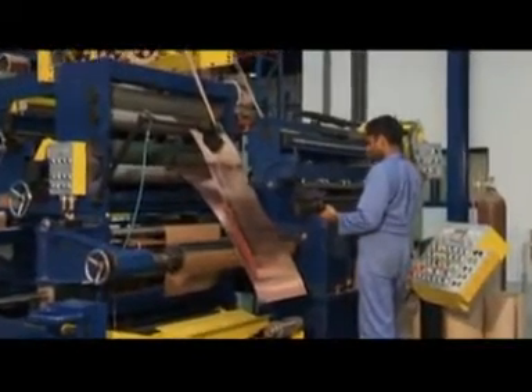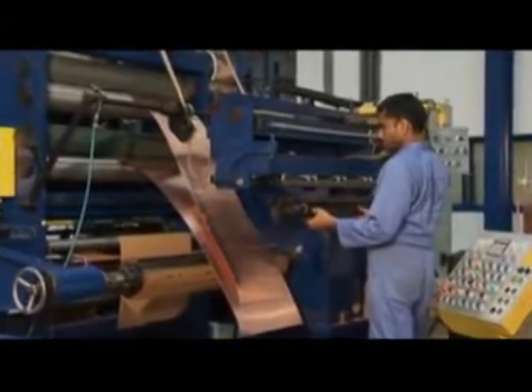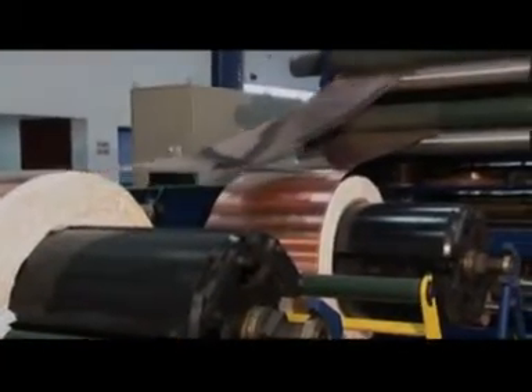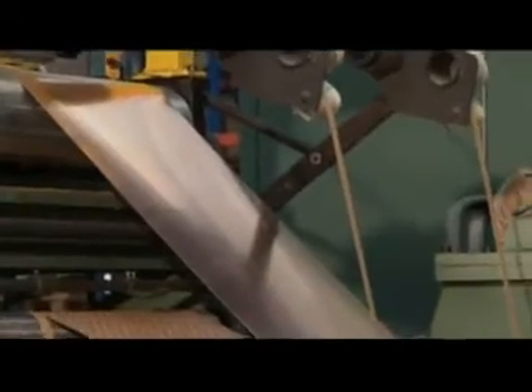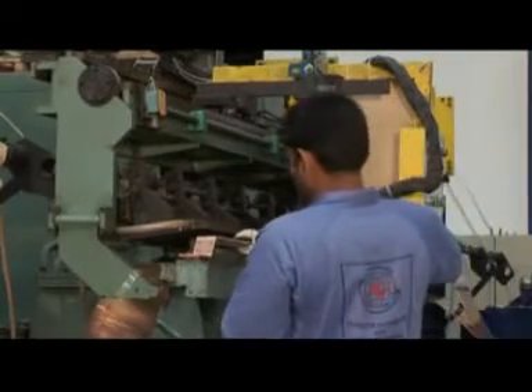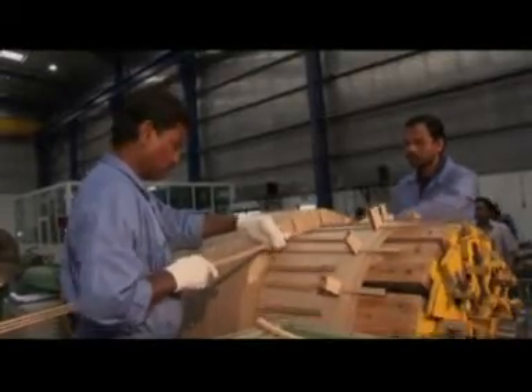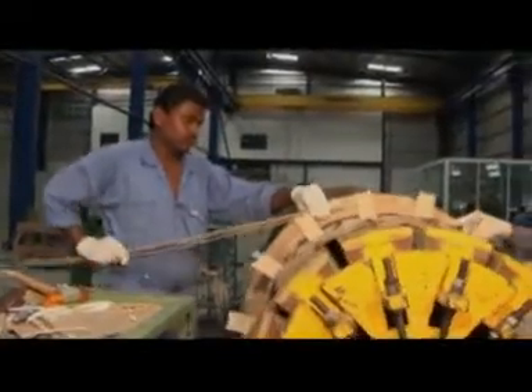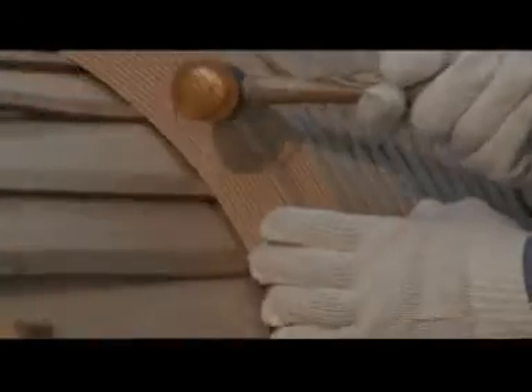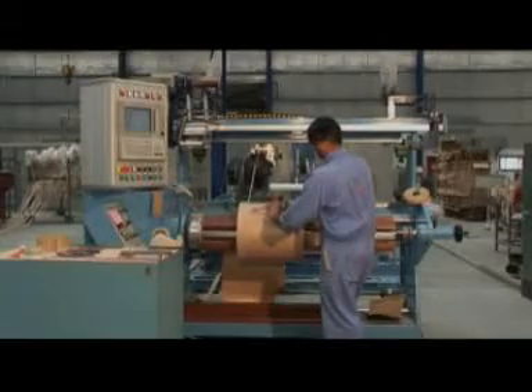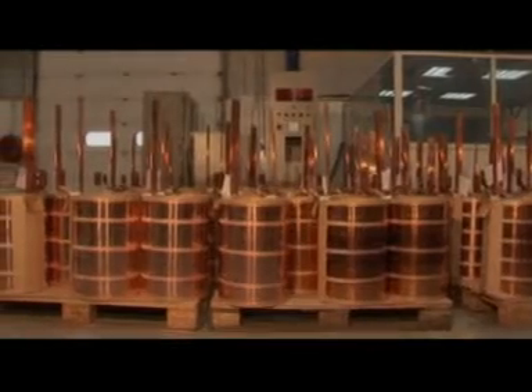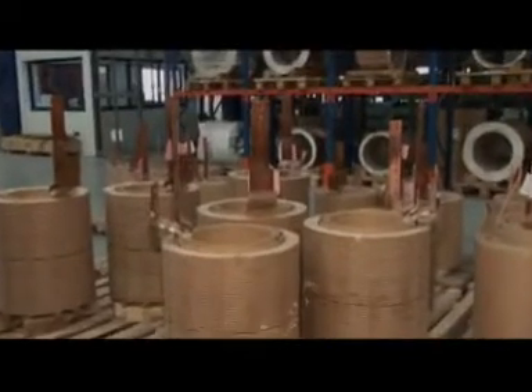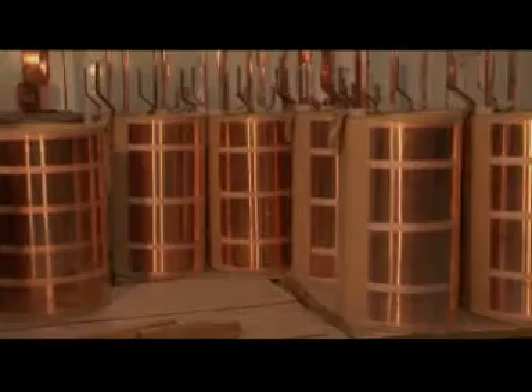Transformer windings are made of very high quality electrolyte grade copper strips. For medium range distribution class transformers, the LV windings are made with electrolyte grade copper foils. HV windings are made with rectangular or round copper conductors. Specially designed winding machines are used for making windings of power transformers. Multiple paper-covered copper conductors are used in making the coils for large power transformers. All windings are designed circular and concentric, which gives the highest resistance against short circuits.